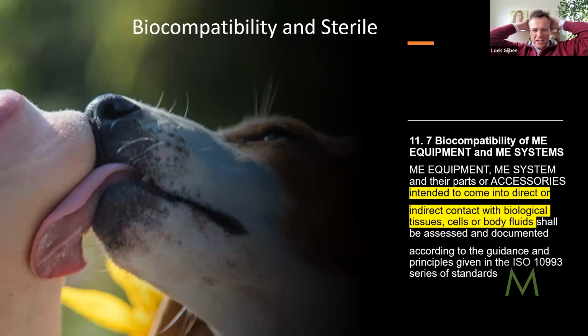Biocompatibility and sterile. That's also a lot. I've seen so many products that, like with ECG cables, you put your connectors to your body, and then the cables hang down on your body and they touch your skin. And they say, oh, the cables must be biocompatible and it's hard and it's expensive. And no, it's not true, because the cables don't have an intention to come in touch with your body. It's only the electrodes. I mean, if you like, you can put a biocompatible Band-Aid on your body and put your cable onto the Band-Aid. And then you don't have to touch it.